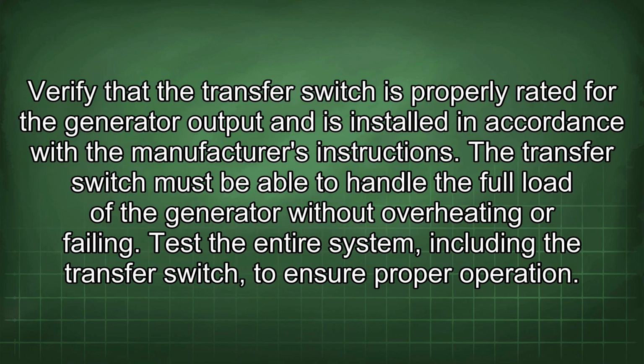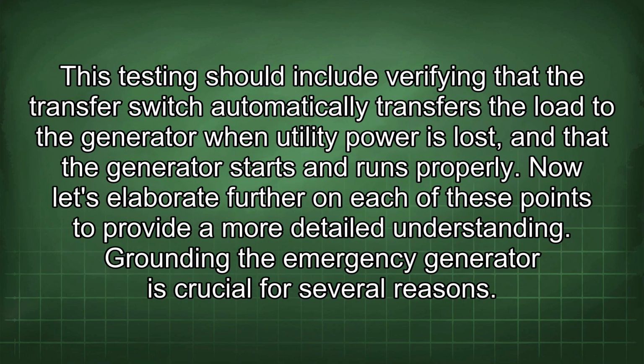Verify that the transfer switch is properly rated for the generator output and is installed in accordance with the manufacturer's instructions. The transfer switch must be able to handle the full load of the generator without overheating or failing. Test the entire system, including the transfer switch, to ensure proper operation. This testing should include verifying that the transfer switch automatically transfers the load to the generator when utility power is lost and that the generator starts and runs properly.